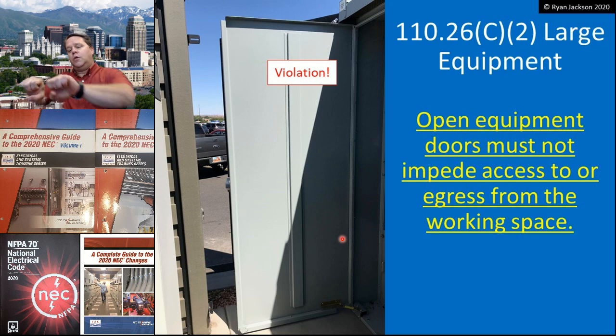Here's the problem. When I open up those 2 doors, each a 36-inch leaf, the little thing drops down into the slot, and now I'm in this little box. If something were to go wrong in there, even with PPE on, I'm in serious trouble. I can't escape through this little 6-inch opening. I'd have to bend down and play around with those little things, and you all know how easy that is sometimes.